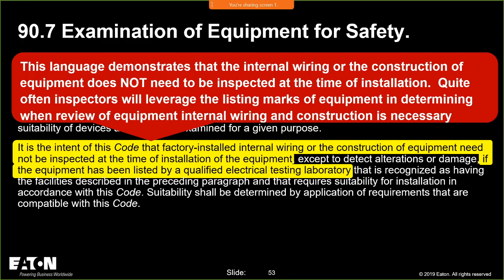Remember, what this section of the code tells us is that the intent of the code is that factory installed internal wiring, this basically says if they're looking at a listing mark, and as long as you didn't modify it, then they're not going to be going into that listed solution and say, well, that wire is not the right size, or this wire doesn't look like it has the right insulation, because it's tested as a unit and it's approved as part of the listing requirement.